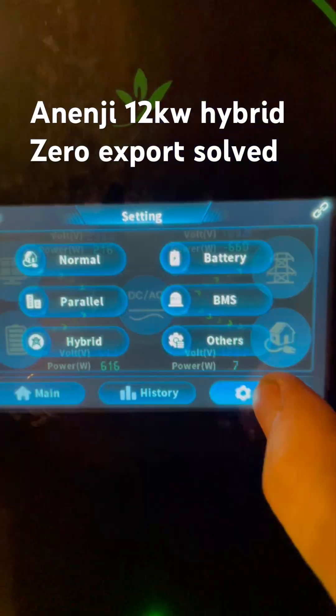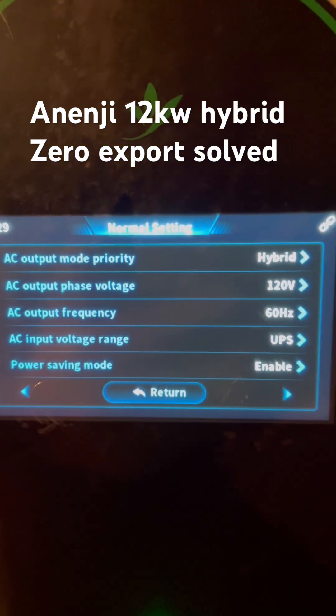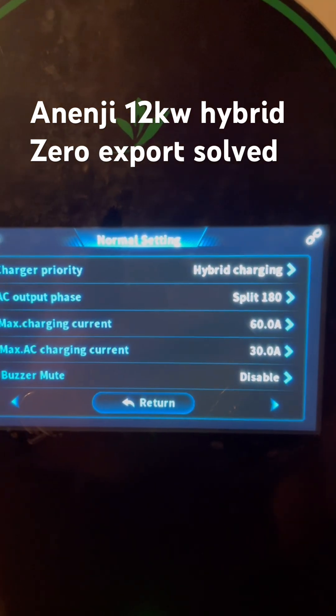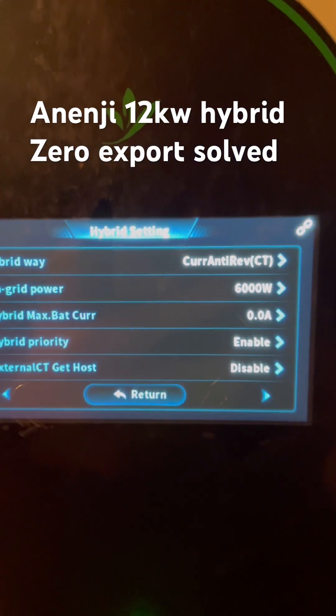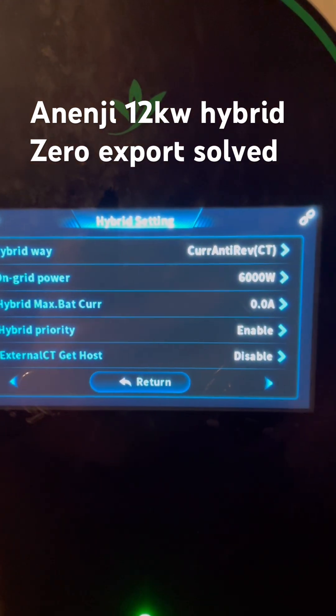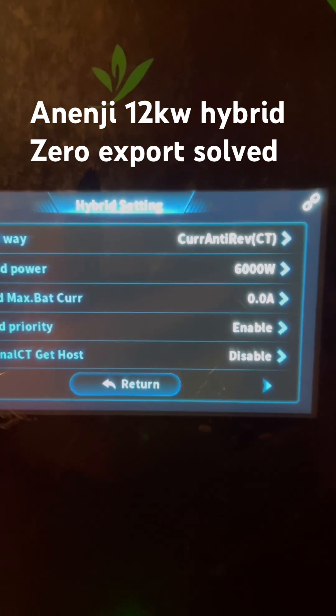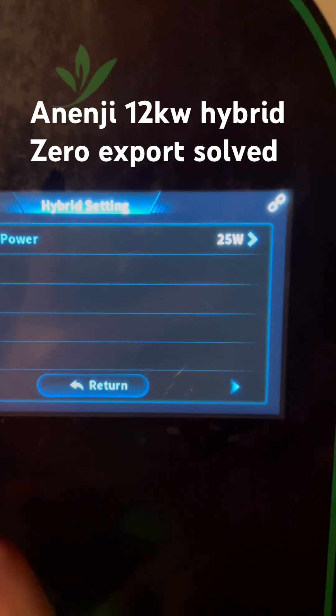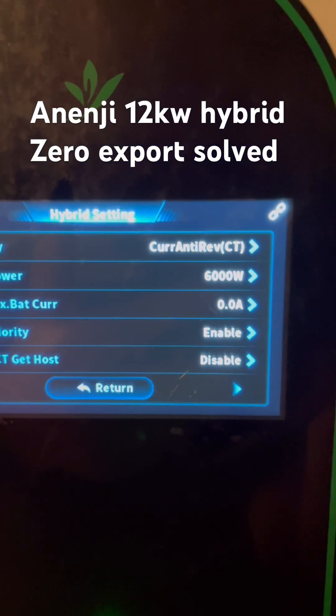So if we go in the settings, I've got it set for hybrid — hybrid charging. We go into hybrid. I've limited it to 6000 watts for now, and I've got Curr Anti-Rev CT set as the hybrid way, with 25 watts of zero export power. And that's it.